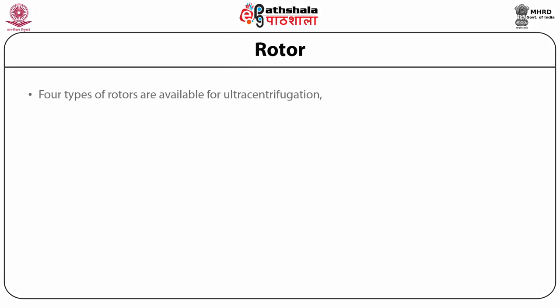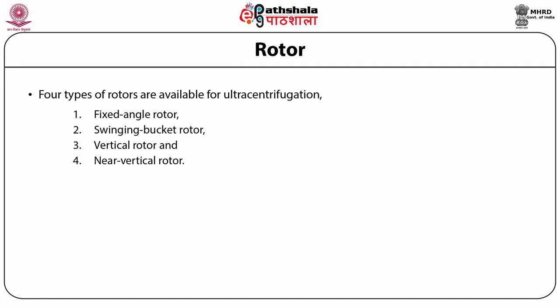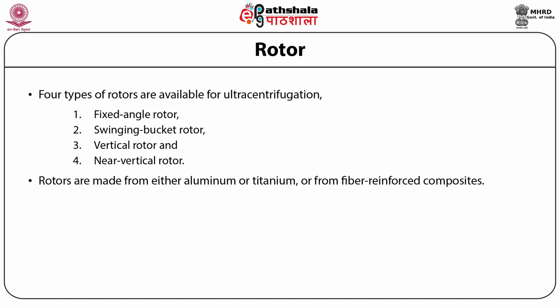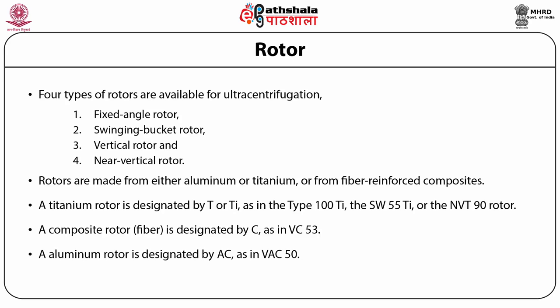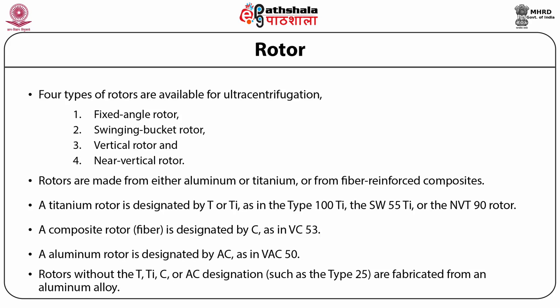There are four types of rotors: fixed angle rotor, swinging bucket rotor, vertical rotor and near-vertical rotor. Rotors are made of either aluminum, titanium, or fiber-reinforced composites. A titanium rotor is designated by 'Ti' — for example Type 100 Ti or SW 55 Ti. A composite rotor is designated by 'C' — for example VC53. An aluminum rotor is designated by 'AC' — for example VAC50. Rotors without titanium, carbon or aluminum designation, such as Type 25, are fabricated from aluminum alloy.